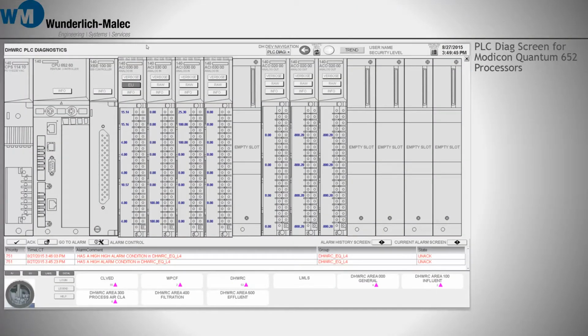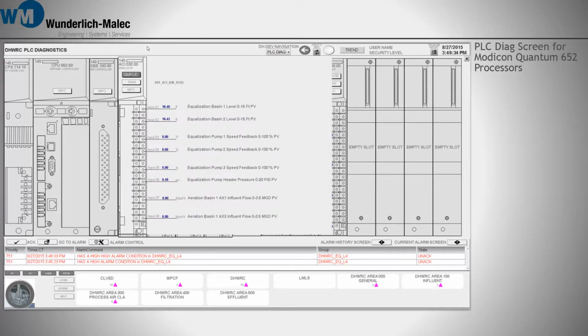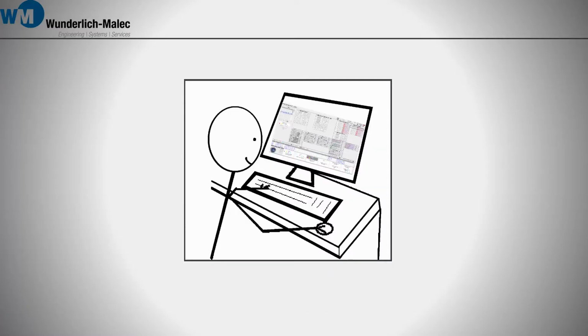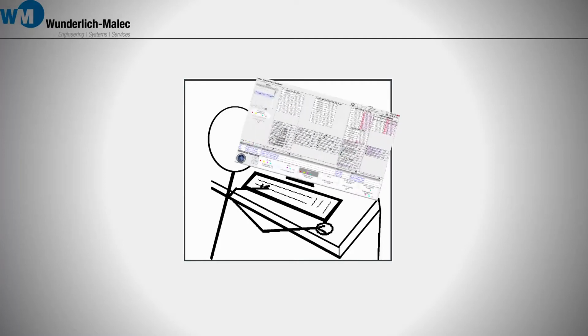For additional troubleshooting, maintenance can use the PLC Diagnostic Screen, which serves as a tool to SCADA for the Modicon Quantum 652 processors. It displays the current value at each rack slot point, and when opened further, gives a description and scaling of the equipment that has landed there. Now, see how an operator views the plant with the help of situational awareness and the new tools available to diagnose a problem.